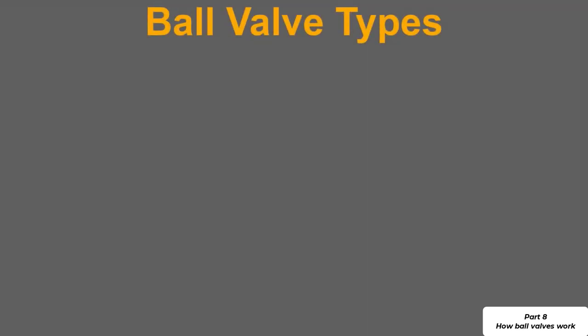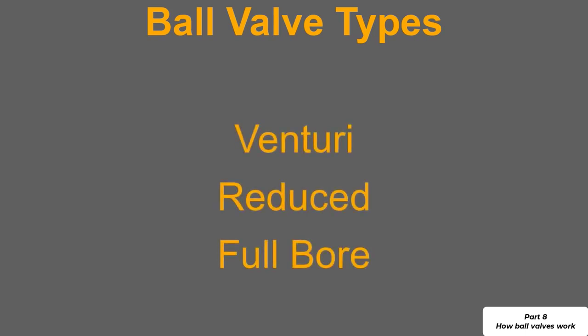There are three different types of ball valve. These are the venturi, reduced and full bore. With a full bore the ball itself will have a flow passage going through it that matches the internal diameter of the piping to which it's connected and this leads us on to some of the advantages and disadvantages of the ball valve.